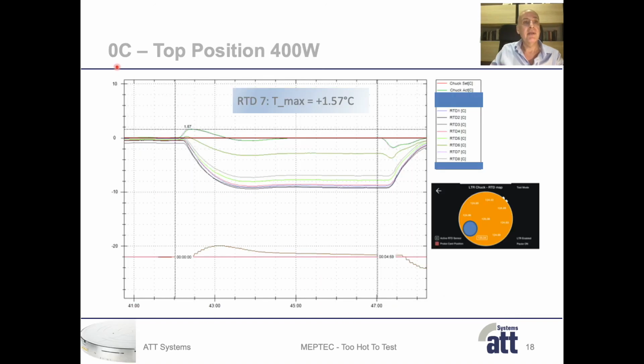The first graph shows the test results at 0 degrees C, top position, with an applied power of 400 watt. This area here is the standby period. So this means the period before we turn on the power, and you can see that all the sensors are very close around the set temperature of 0 degrees C. Then here we turn on the power, 400 watt, and we can see a temperature increase of around 1.6 degrees C. RTD7 detects the temperature increase and became the control sensor.